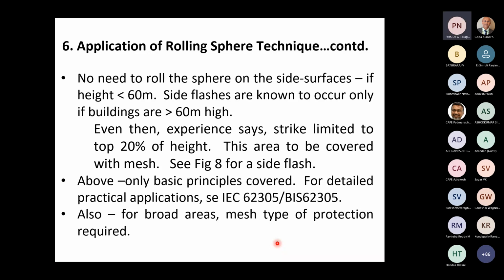Now, again, I'm repeating this. No need to roll the sphere on the side surfaces if the height is less than 60 meters. In such a case, side flashes practically are not seen at all. Therefore, there is no need to give protection on the side surfaces of buildings which are less than 60 meters tall. Side flashes, on the contrary, are known to occur only on buildings which are more than 60 meters high.